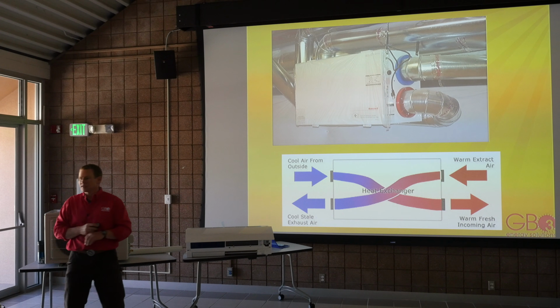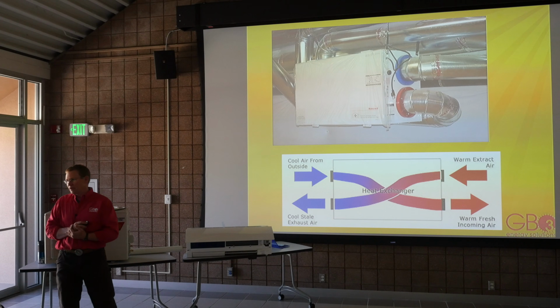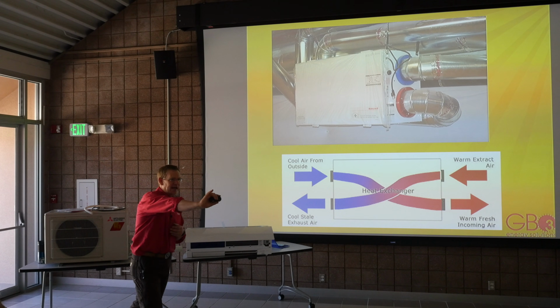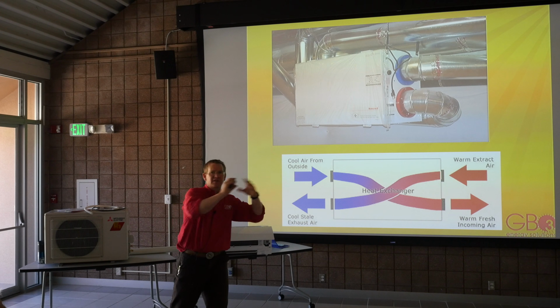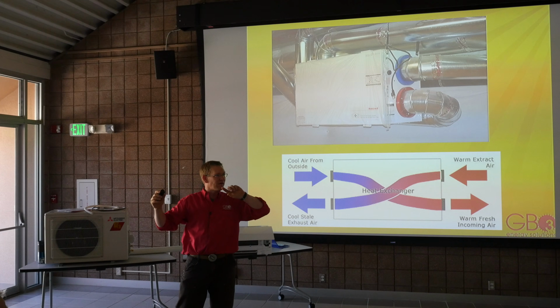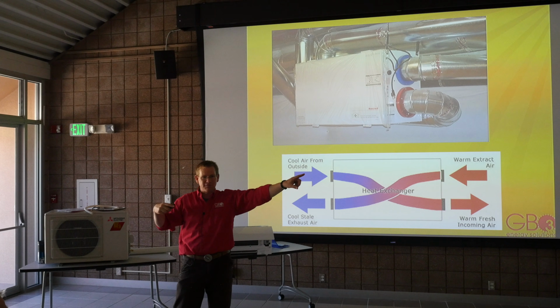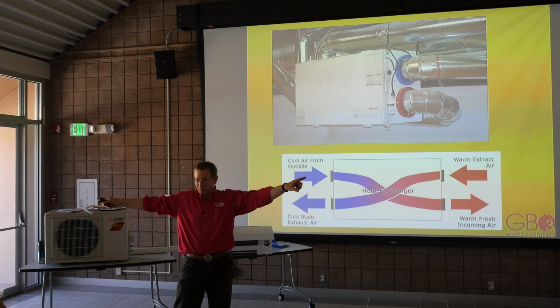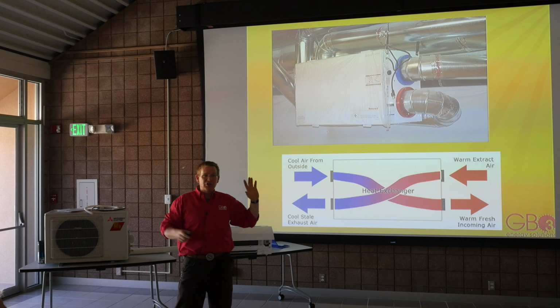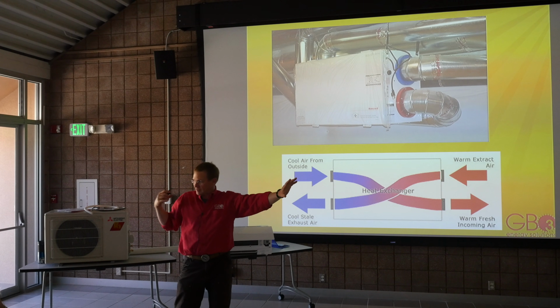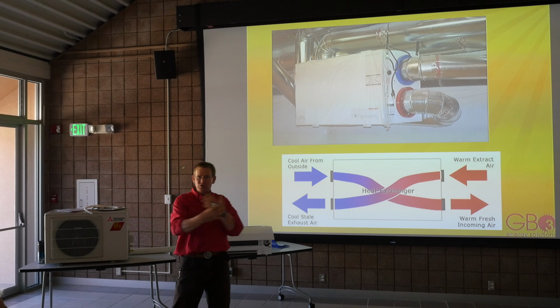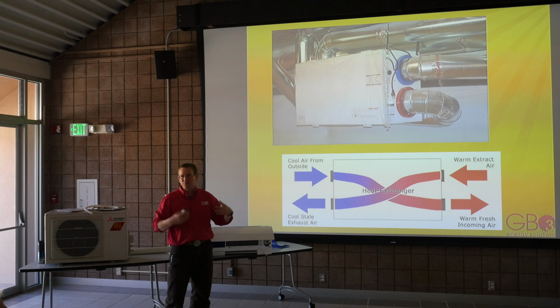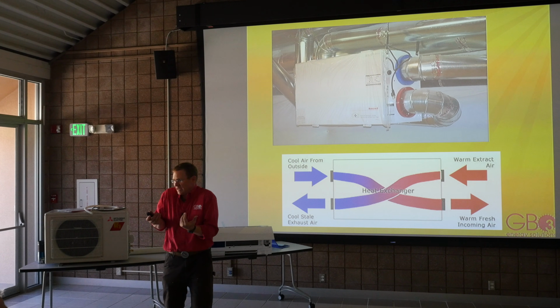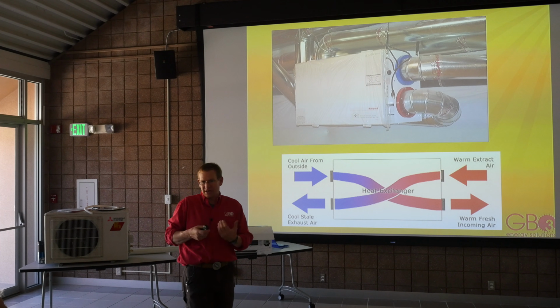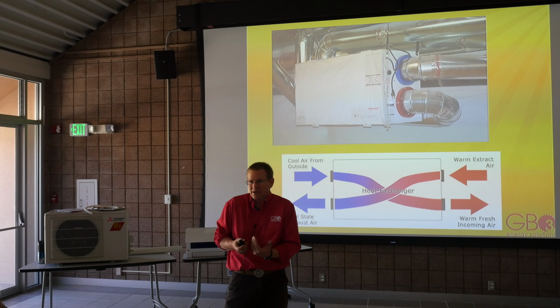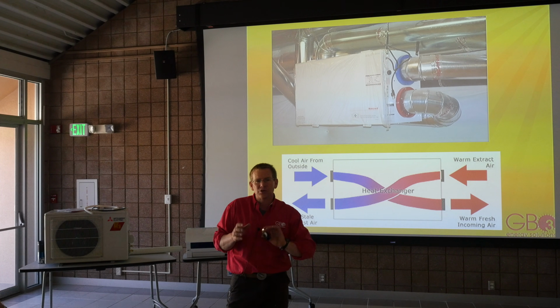So, thanks Todd - this is an energy recovery ventilator. Instead of just exhausting air outside, remember this isn't a balloon, it doesn't change volume - if a cubic foot leaks out, a cubic foot leaks in, whether it's 100 degrees or 0. That's just physics. So rather than bringing in air that's 0 in winter or 100 in summer, it goes across a heat exchanger, and we're able to recover the energy and humidity from it. These are very efficient units - we're getting close to 90+% efficiency on some now, and they don't use much electricity either with the new ECM fans.